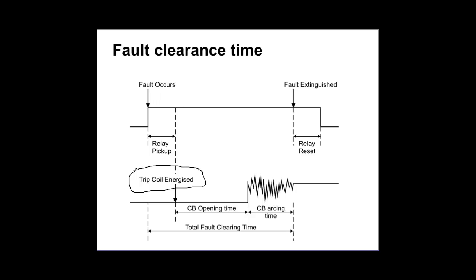Nope. Again, the circuit breaker contacts try to separate. So can I say at the time of separation, exactly at the time of separation, the circuit breaker is open and the fault is clear? No. Well, still the arc is there. So it takes some time for the arc to move away, and it all depends on the insulation material and the distance of the two contacts of the circuit breaker. So it takes some time for the operation of the circuit breaker. And it takes some time for the operation of the relay.